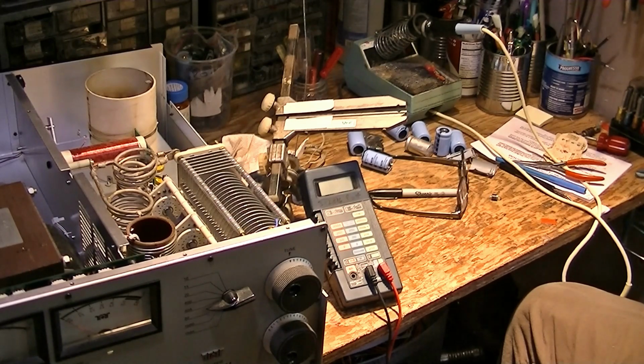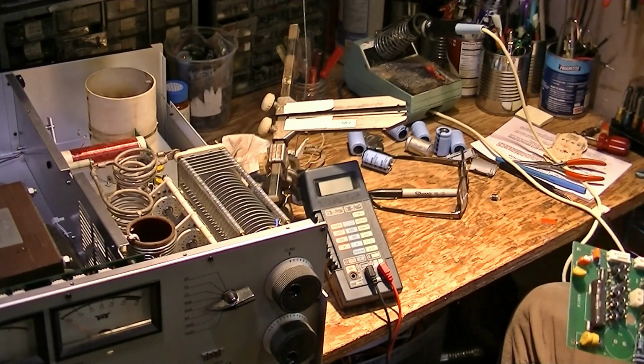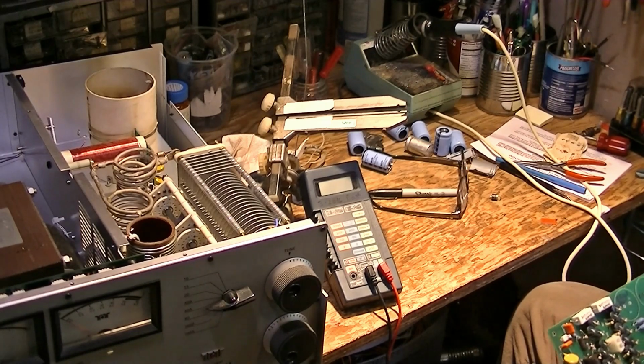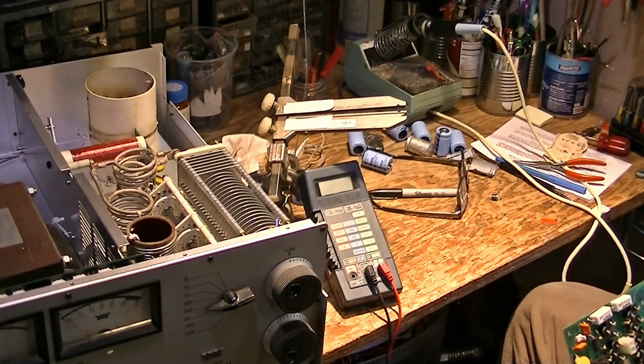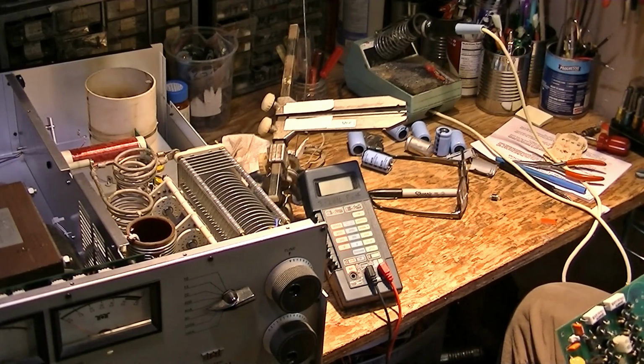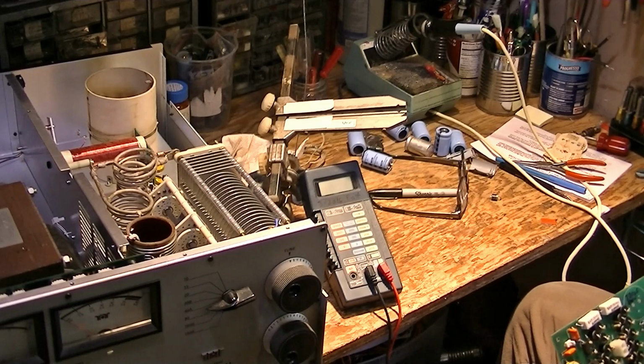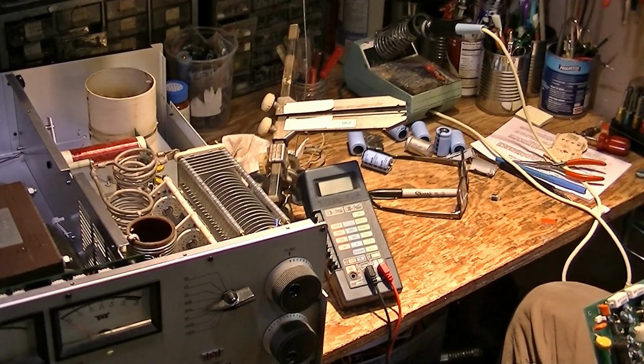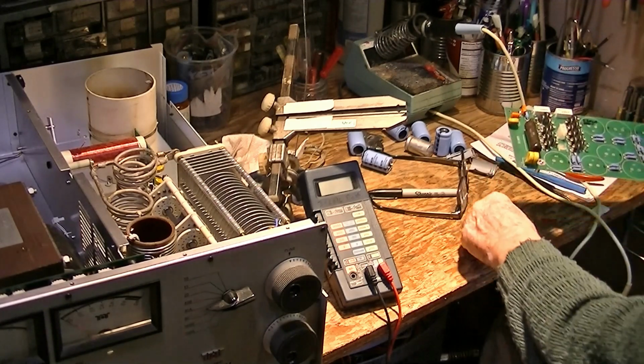And then we'll get the new capacitors and put them in there. I said this wrong - there's 9 of these capacitors instead of 8. So 9 times 400 is 3,600 working volts, and the calculated voltage is around 2,900. So that's about 700 volts of ceiling, which is about 25%. So that should be pretty good. I said 8, but there's 9.